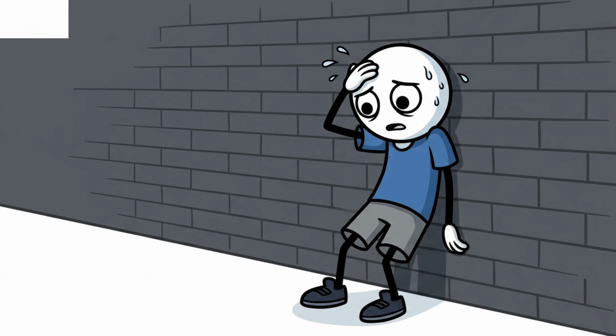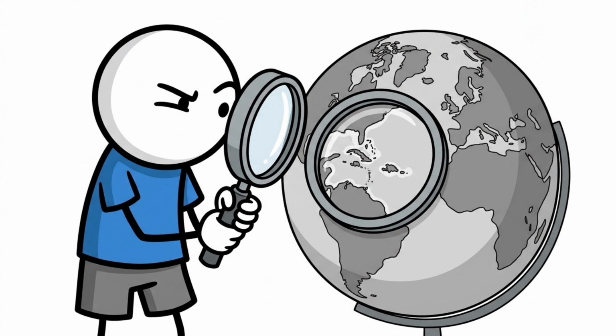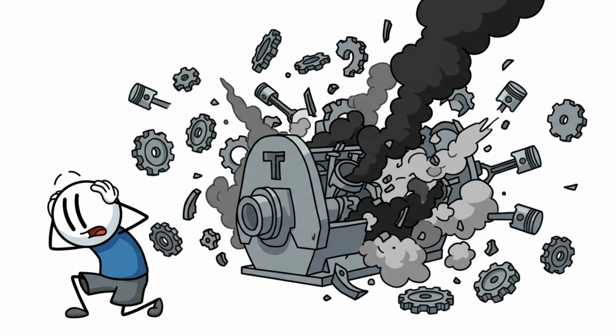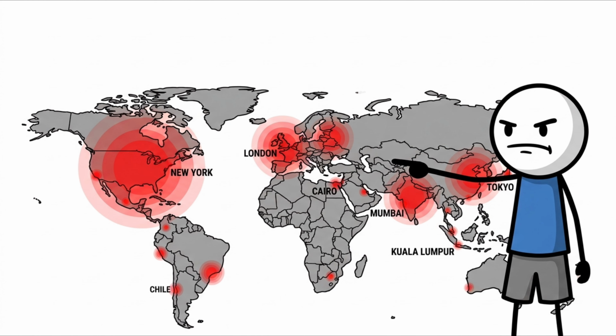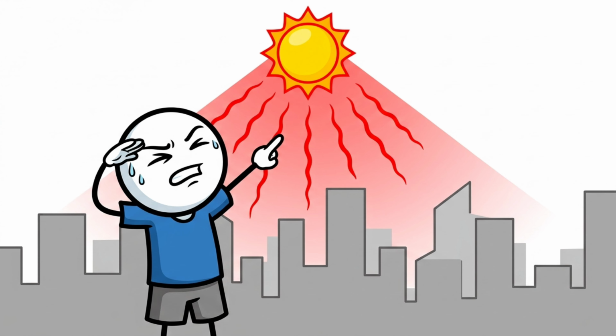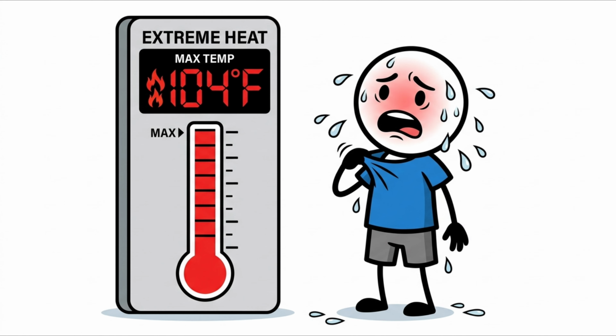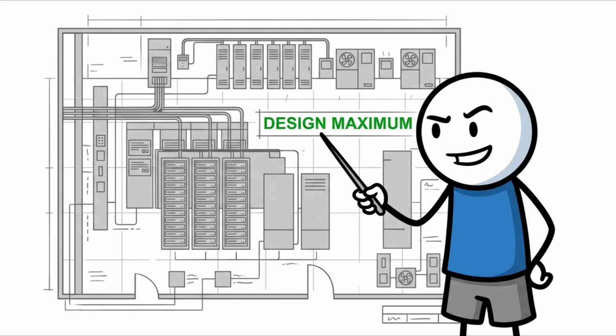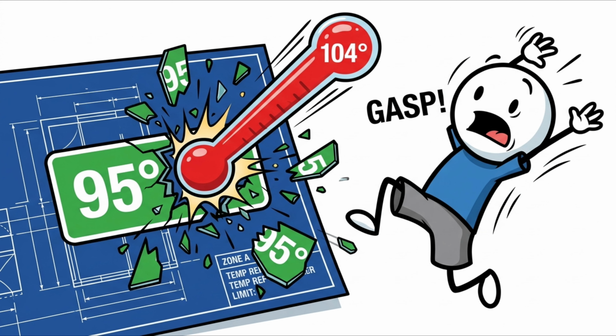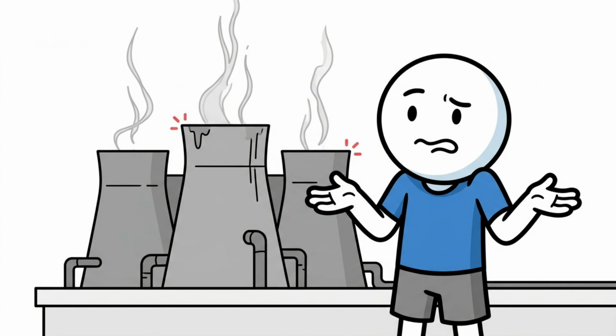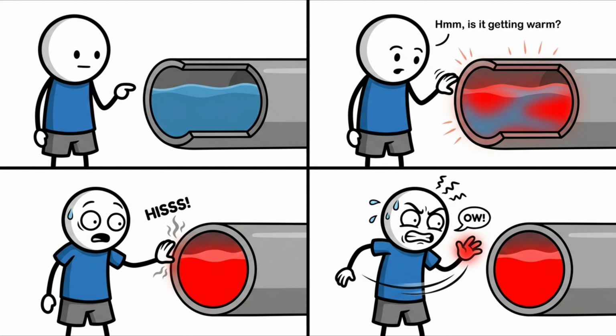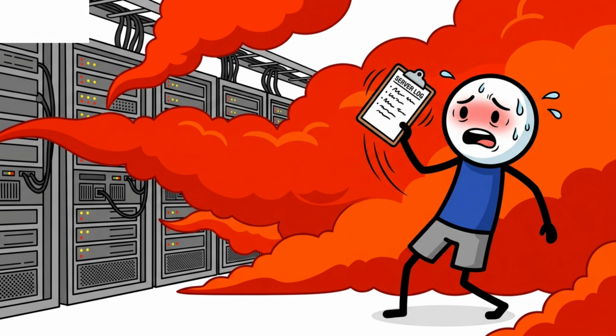To understand how this plays out in the real world, look at what happens when the thermodynamic engine actually fails, and at the major outages that hit the industry every few years. A heat wave strikes a major city. The temperature outside hits 104 degrees, but the data center was designed for a maximum of 95. The cooling towers on the roof cannot reject heat fast enough, the chilled water loop starts warming up, and inside the data center hall the temperature climbs.